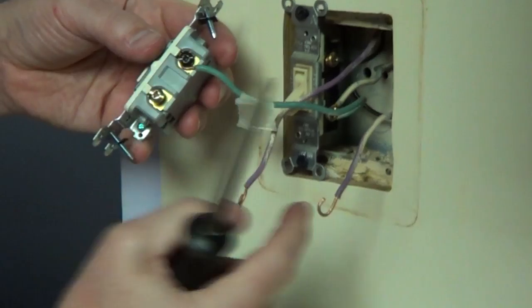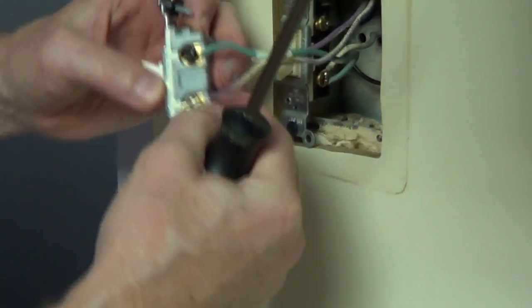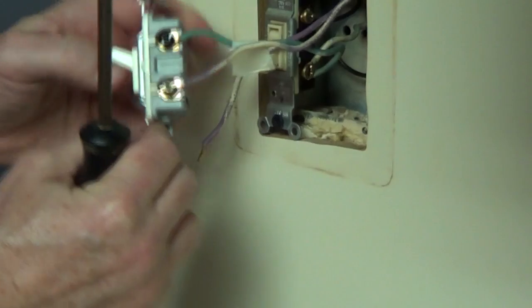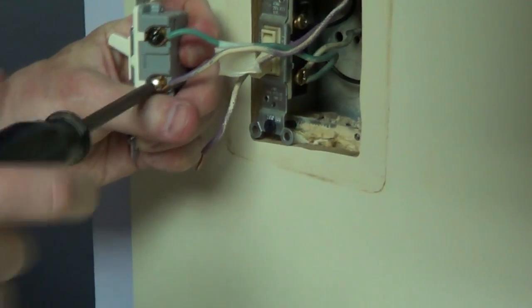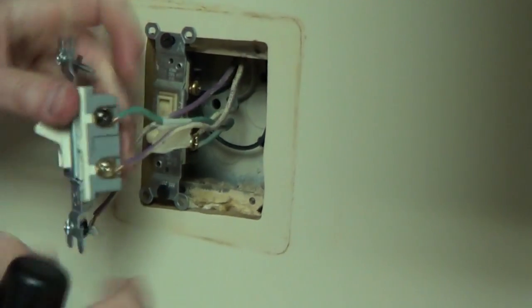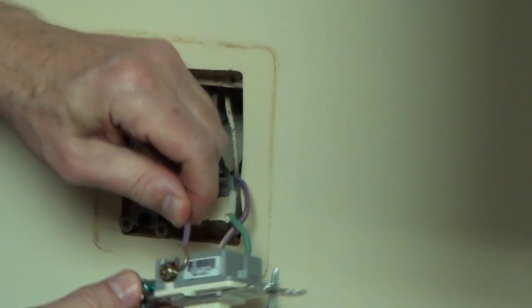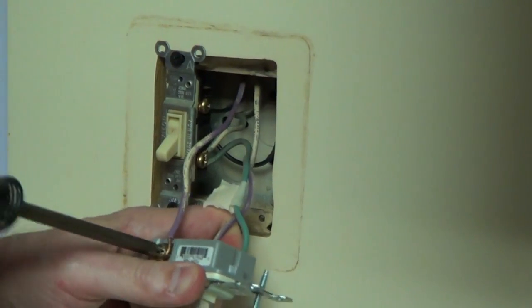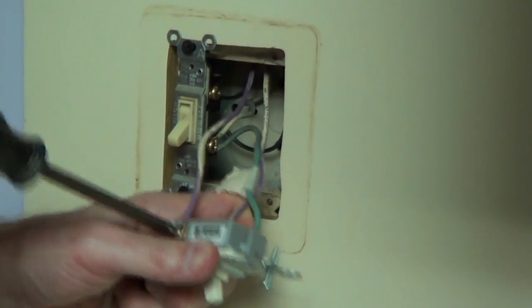Now the other two wires are our travelers. These wires go to the other three-way switch, and it doesn't matter which screw terminal you put them on. Just connect them and make sure you hook it in a clockwise direction. That's all there is to connecting the new three-way switch.